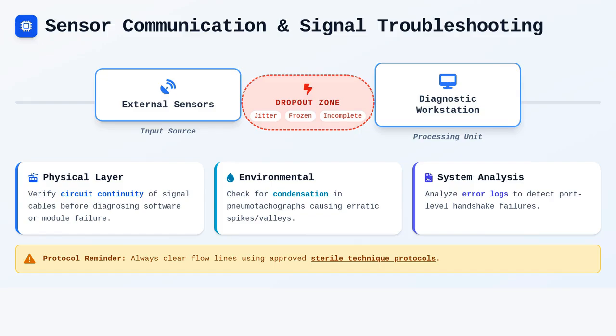Communication dropouts between the external sensors and your diagnostic workstation often manifest as jittery, incomplete, or frozen digital signals. When this happens, verify the physical circuit continuity of the signal cables before assuming a software crash or an interface module failure. Moisture condensation is another subtle but common offender, especially in flow sensing equipment, where small droplets can distort the laminar flow and create irregular, erratic readings on your display. If you detect unexplained spikes or valleys in your flow volume loops, check for condensation inside the pneumotachograph and clear the lines according to your laboratory's sterile technique protocols. Should the issue persist after ensuring the pathway is dry and the cables are secure, analyze the system error logs to pinpoint if the communication handshake is failing at the port level.